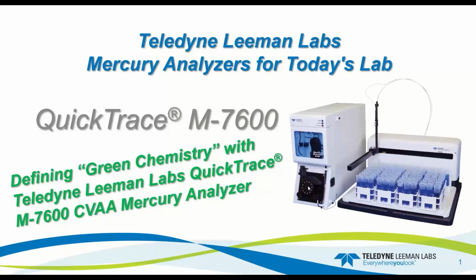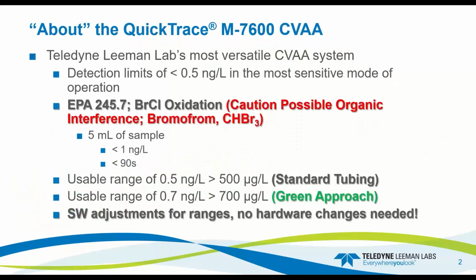So this is the M7600 here, peristaltic pump, gas liquid separator in here, and this is coupled with the ASX 560 autosampler. So in order to discuss the green chemistry and how we accomplish that with the M7600, I'm going to give you a short background on the system, how it works, and then a little segue into the new pump tubing, which is how we accomplish the green chemistry, and then the ease of implementing the green chemistry via the QuickTrace software. And then we'll discuss some of the results from the testing, and then also the analytical results as well that we use to implement the new tubing harness.